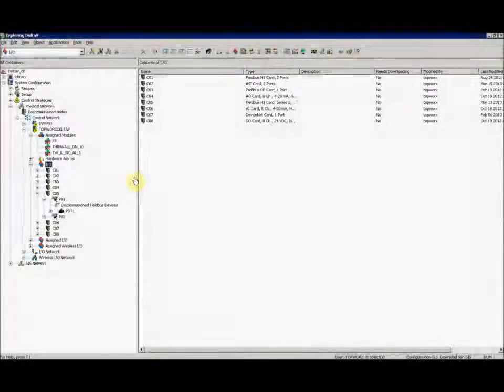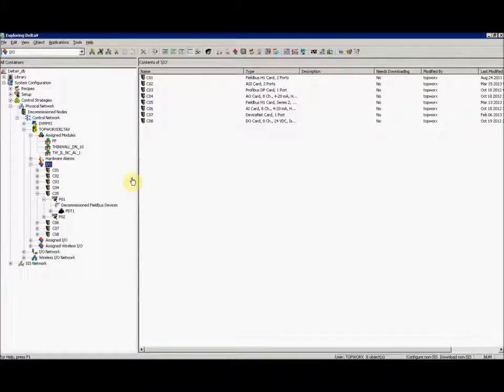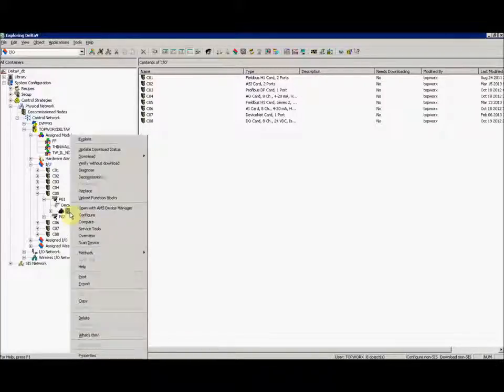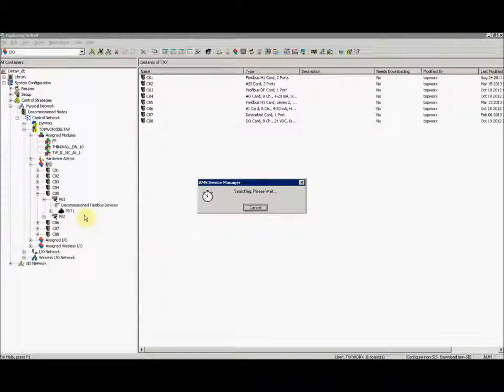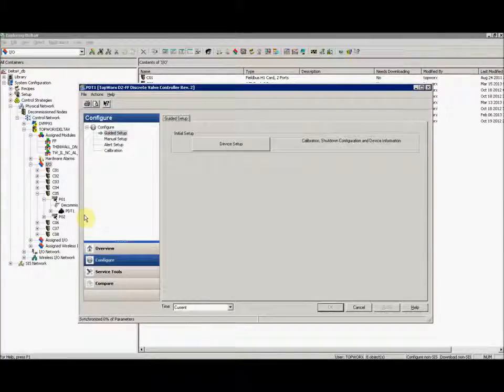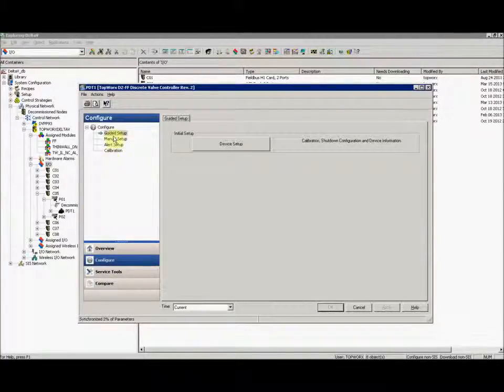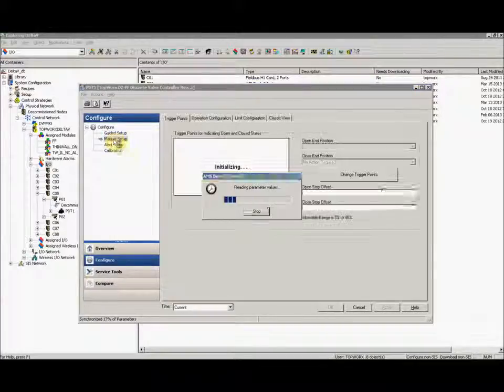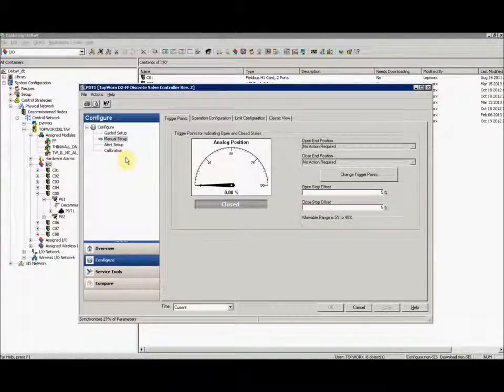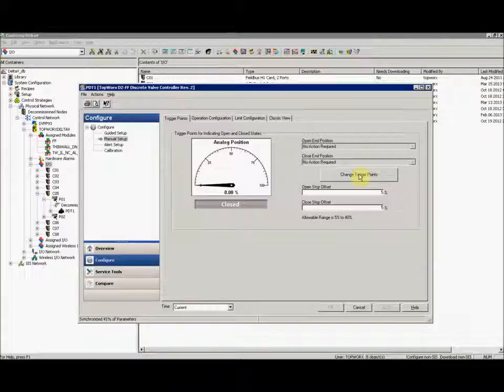Once your device is commissioned, you can stroke your valve between open and close through AMS. To do that, right click on your device, select configure, then select manual setup. Click the button change trigger points.